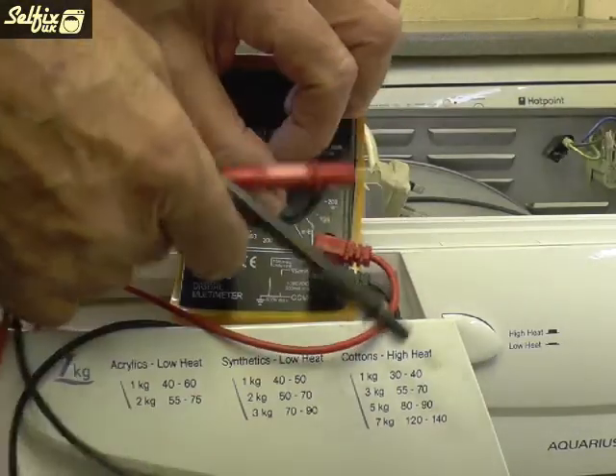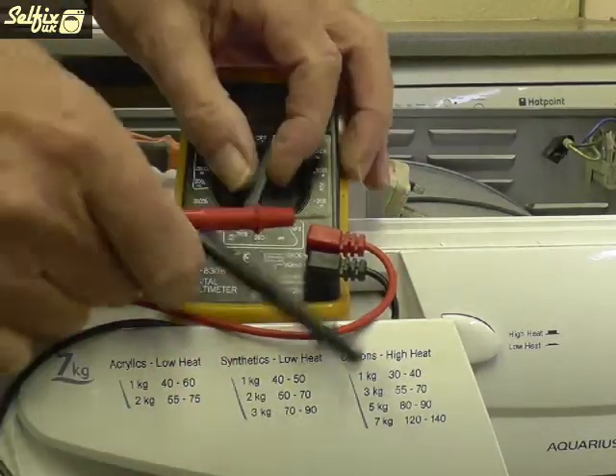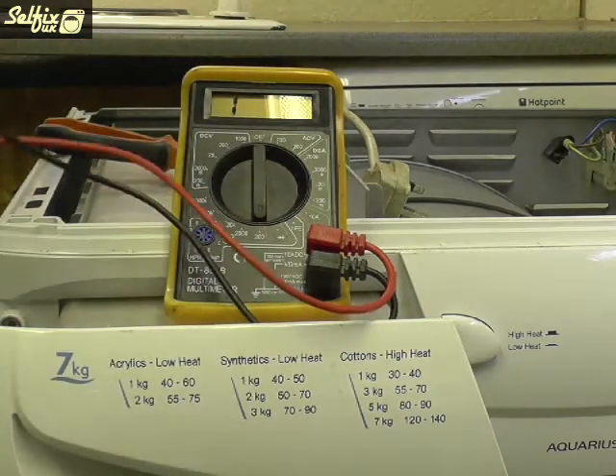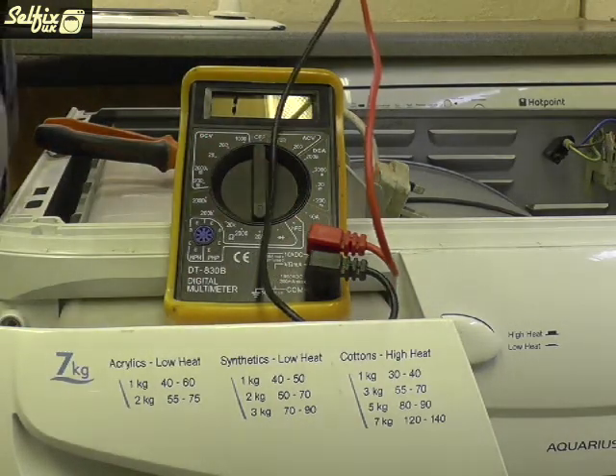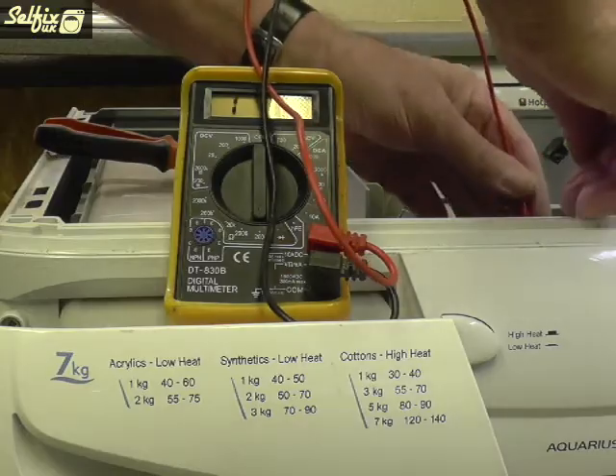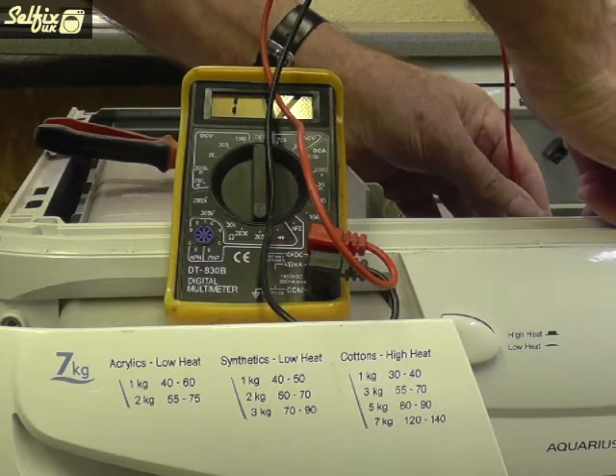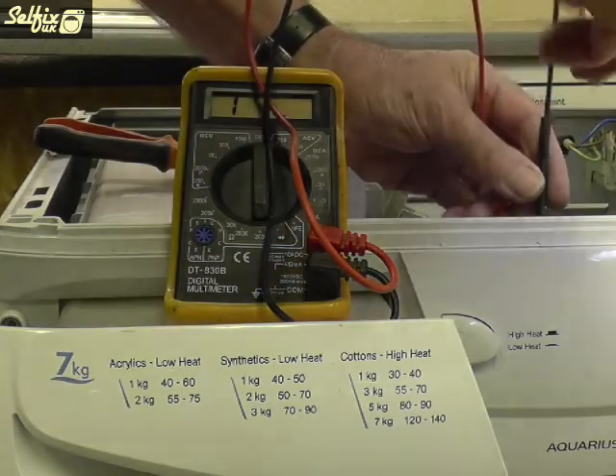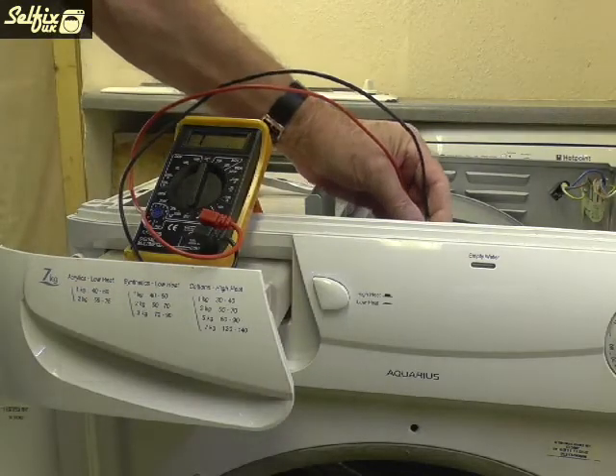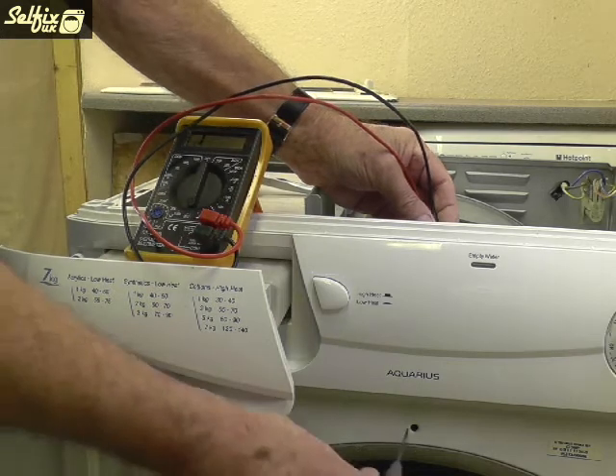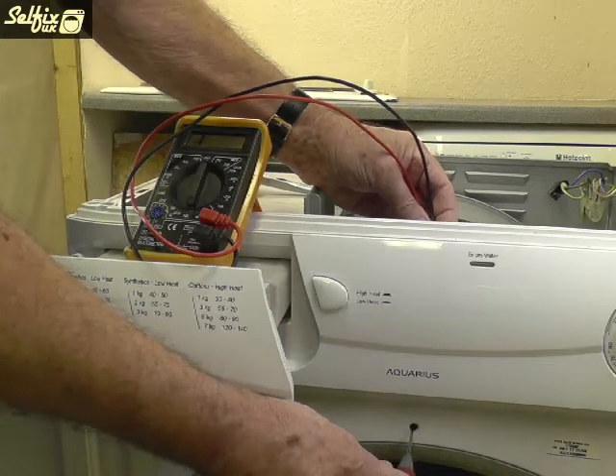Take the wire terminals off the switch before testing, because to test it with them on will only give you a false reading. Set your meter to the 200 setting and touch one probe on each of the terminals of the switch. If possible, keep the probes on the terminals whilst activating the switch with the aid of a thin screwdriver. If there's no reading on your meter, the switch needs replacing.